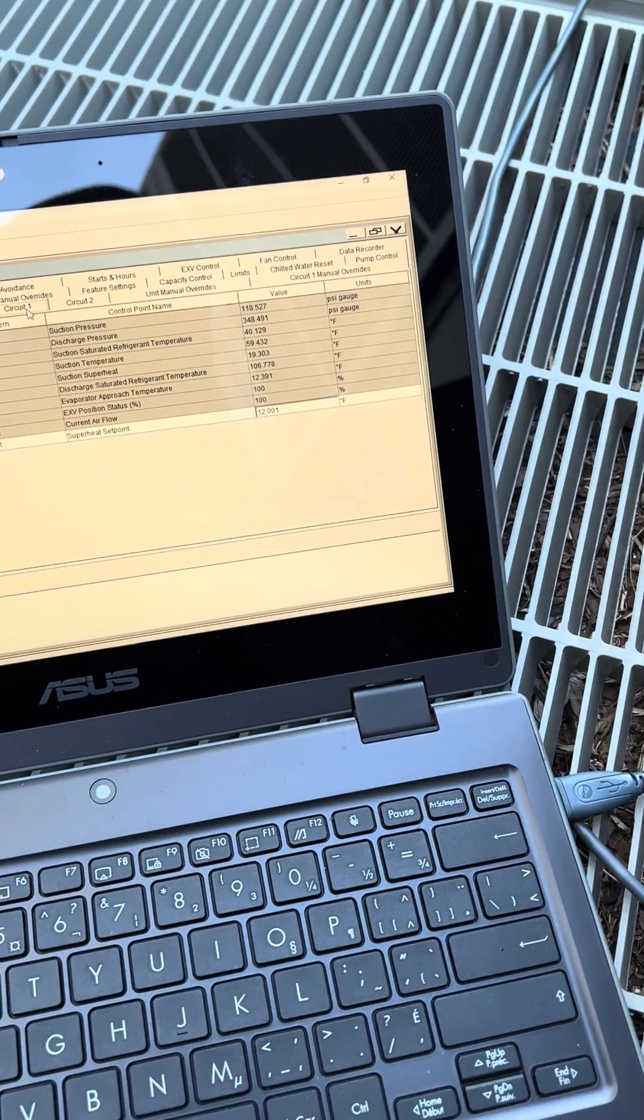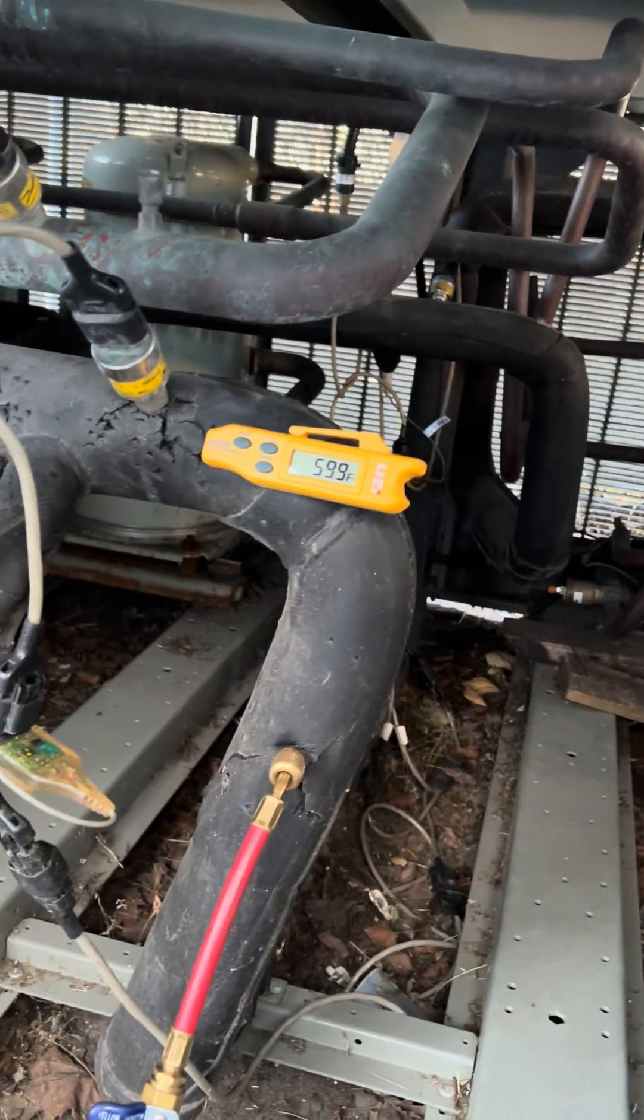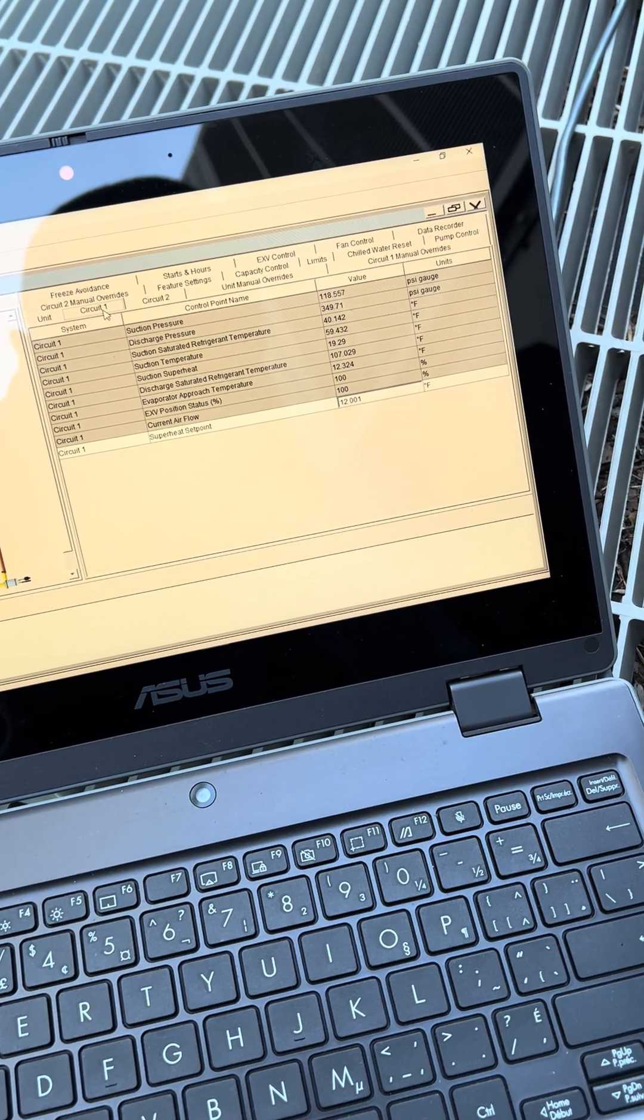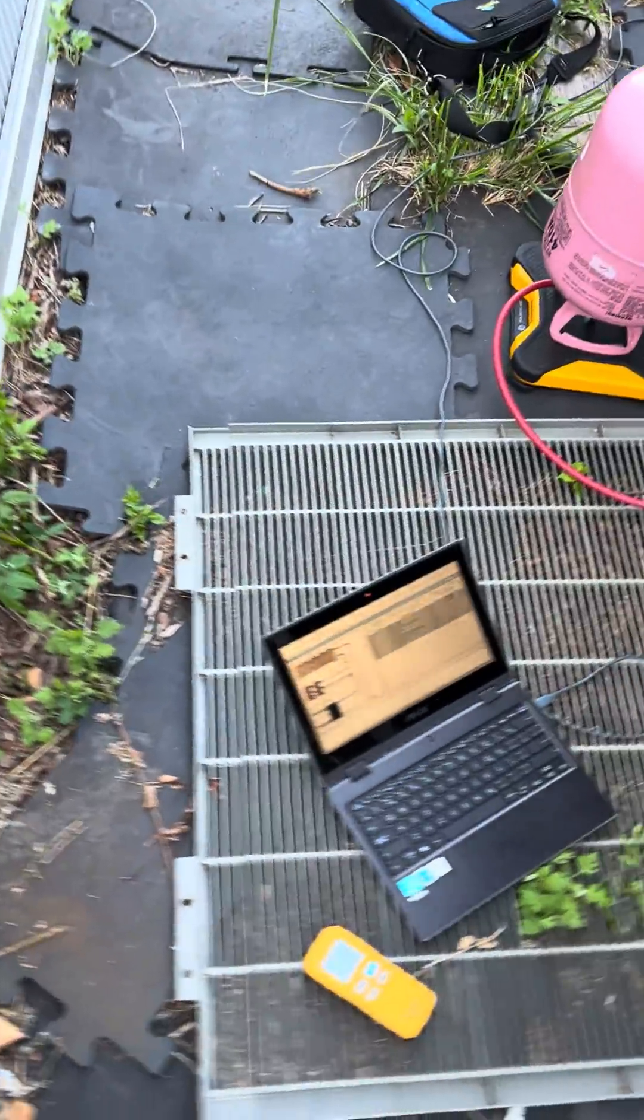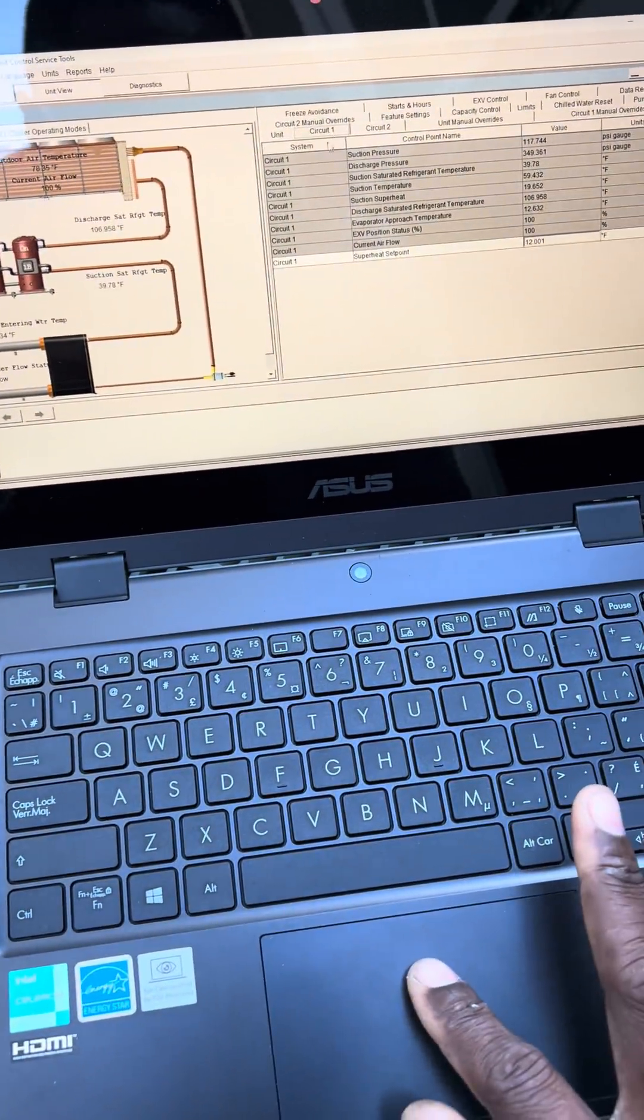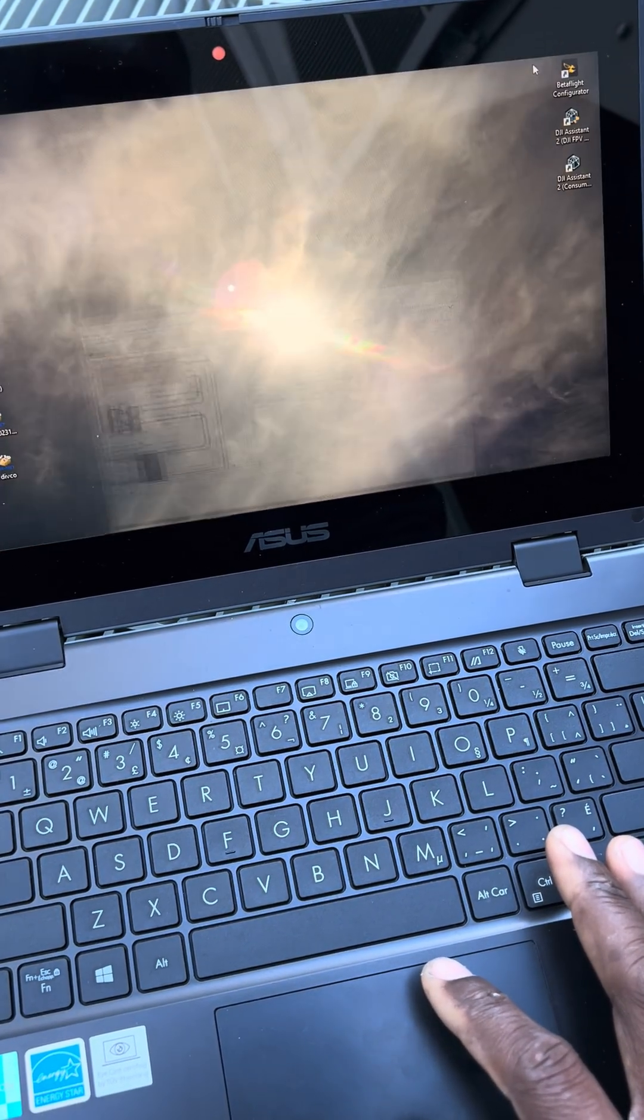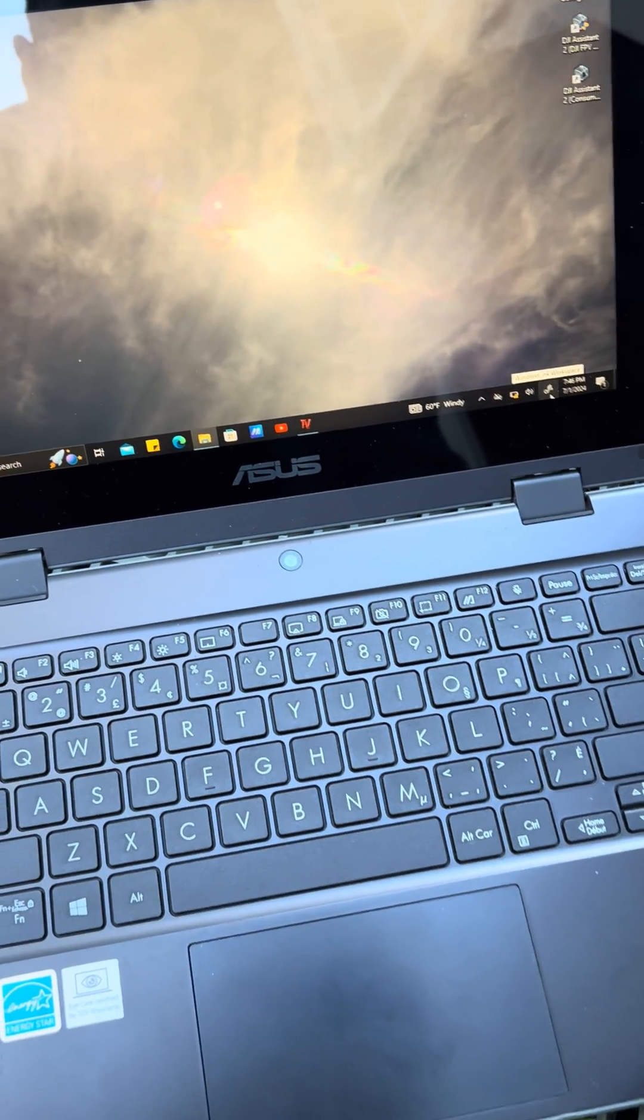All right let's see where we're at. We're at 19 degrees superheat with two pounds added and my suction line is 59. So I'm gonna monitor this thing for a little bit and then I might just add another pound and then see how it pans out. Like this video if you think this video is dope. I'm gonna keep doing this until my laptop battery goes out. I should just close the screen and minimize it and put it to sleep so we can save energy.